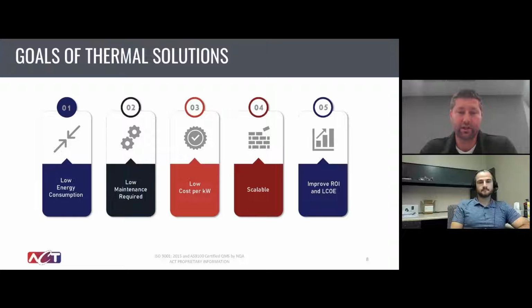Scalable solution is another factor. Pretty much every product we'll talk about, especially the dielectric-based passive and active two-phase technologies, will have a scalable component. They're very scalable, and we'll show examples rejecting a couple hundred watts to a kilowatt of heat, all the way up to a couple hundred kilowatts, with the same technology just by scaling the form factor. We'll also look at ROI and levelized cost of energy, the LCOE, of these various technologies, looking for the implementation and usage to match the economics of the system.